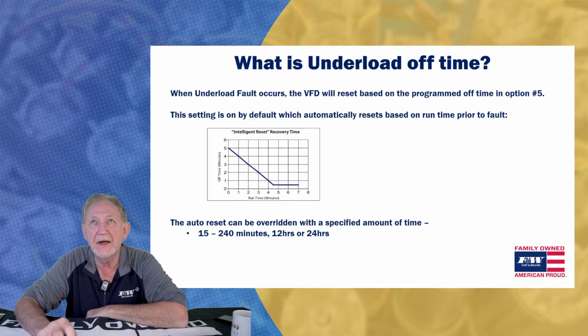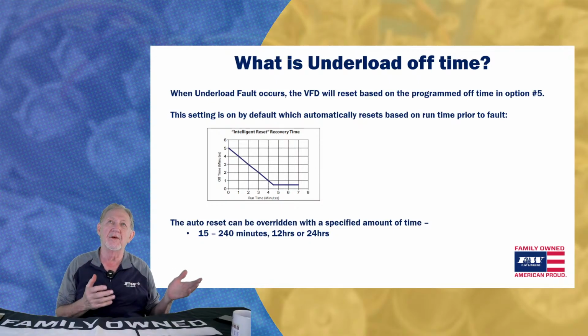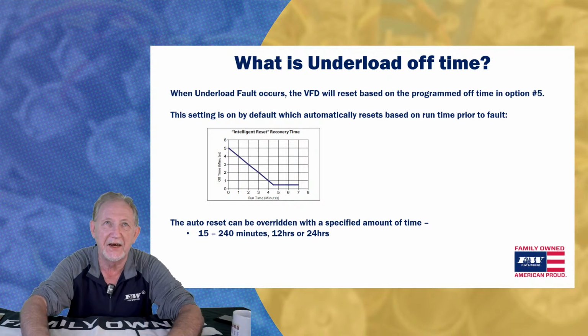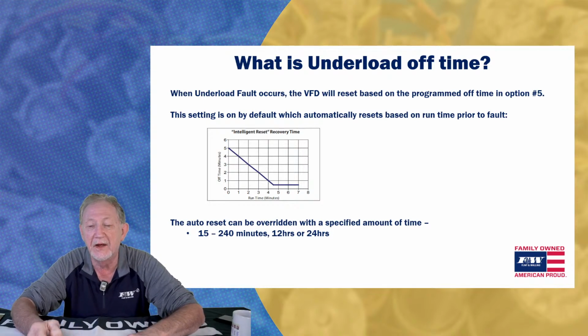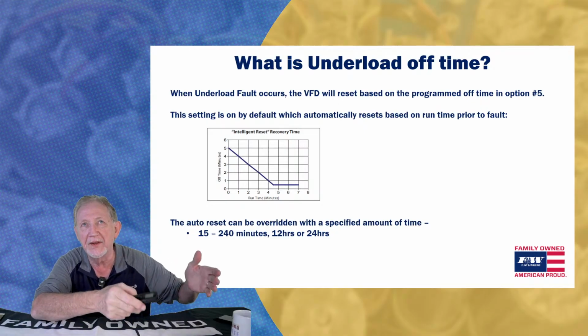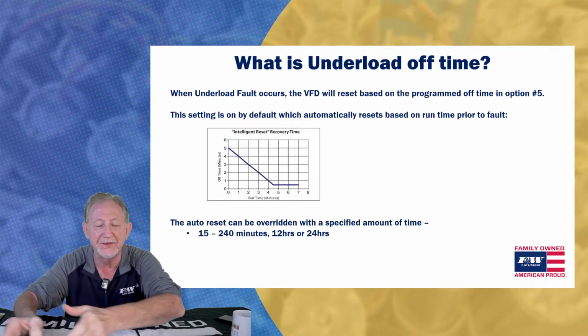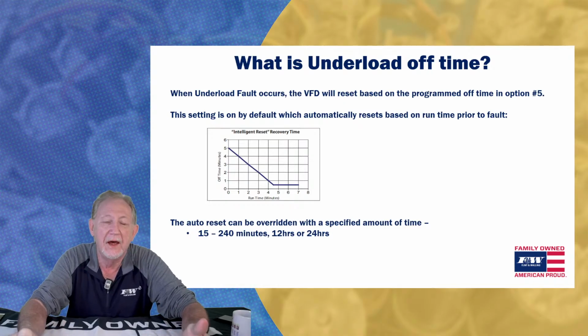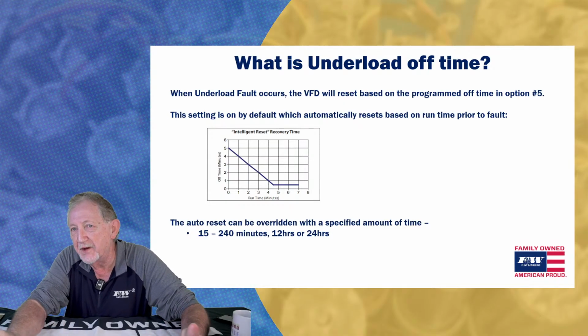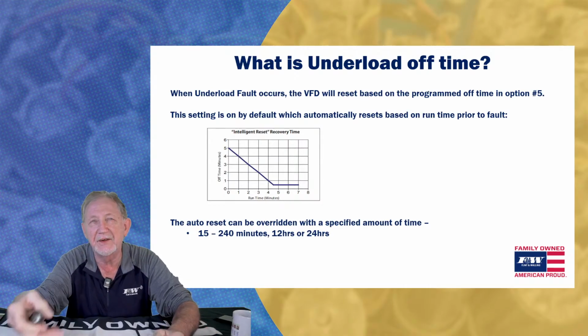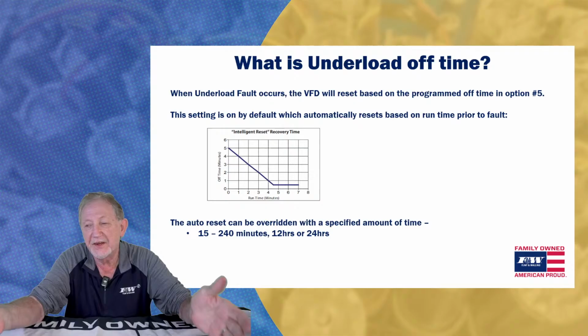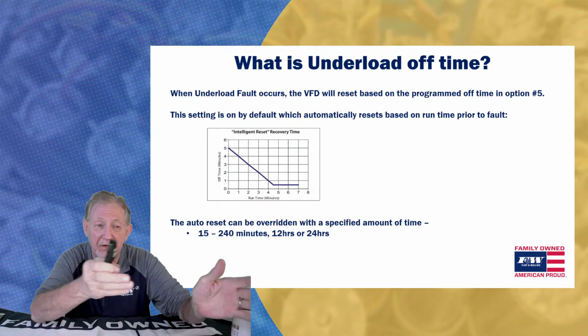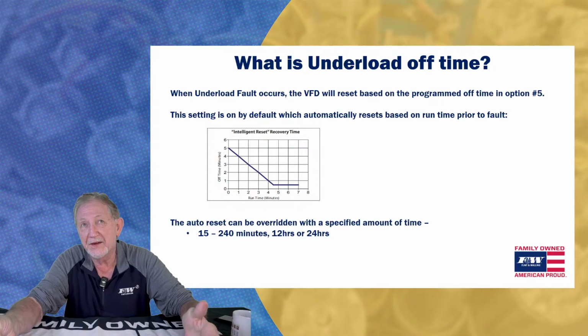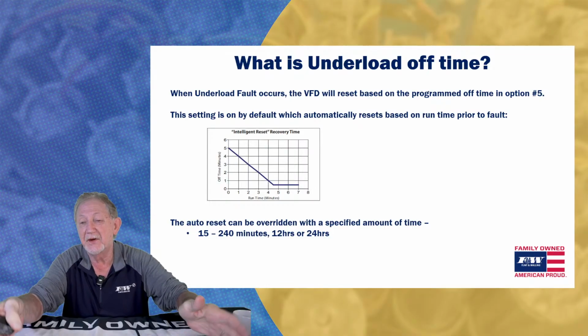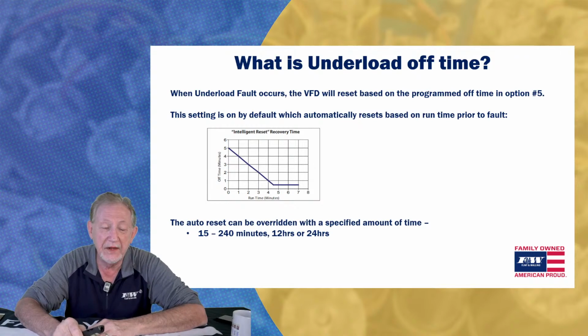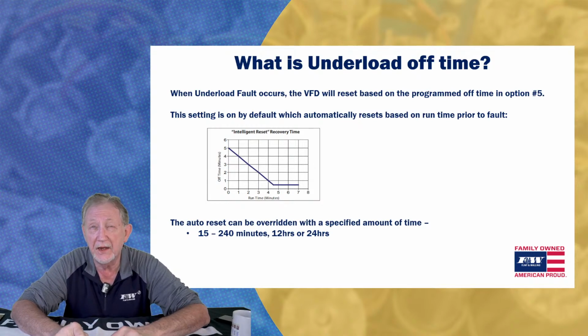And when that happens, when that drive goes into a fault, this has what we call intelligent reset. That drive's going to go back and determine how long that pump ran prior to that fault taking place. Therefore, it's going to determine how long it needs to keep that pump off for the system to recover. And that drive will come back on and determine whether that condition, in this case either a deadhead or a dry run, still exists or not. Based on that, it'll either continue to operate fine, or it'll go back in and shut off again.